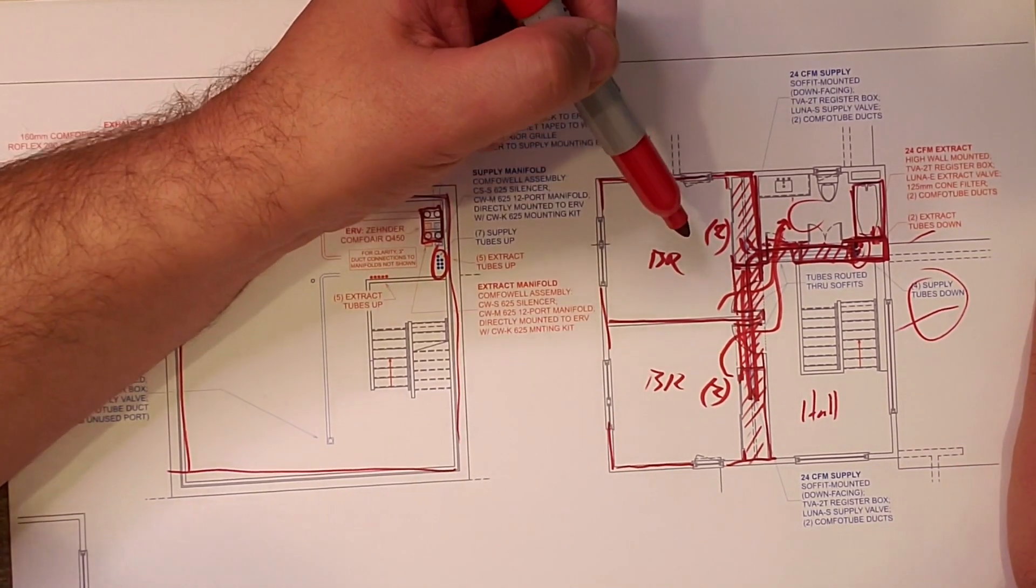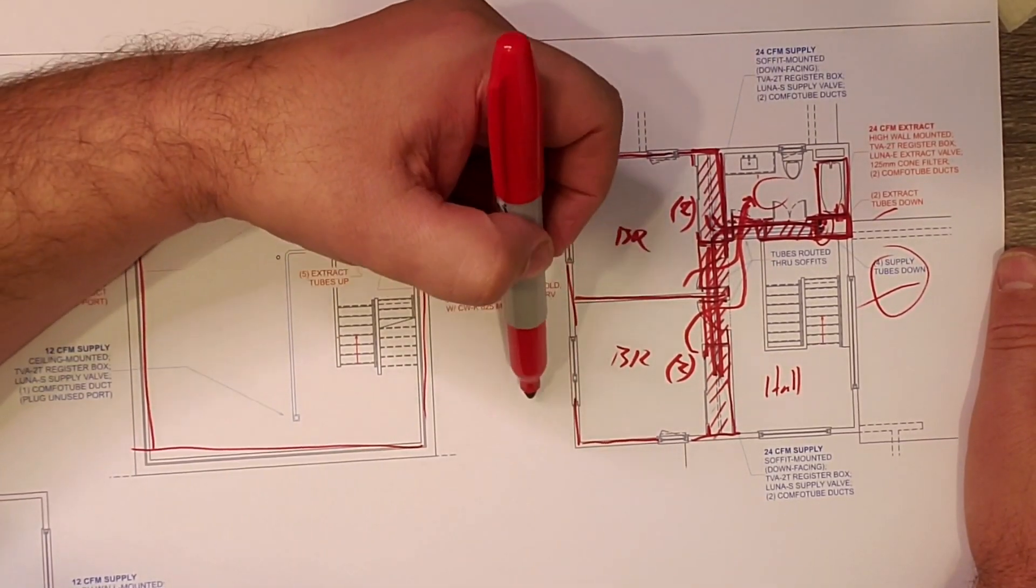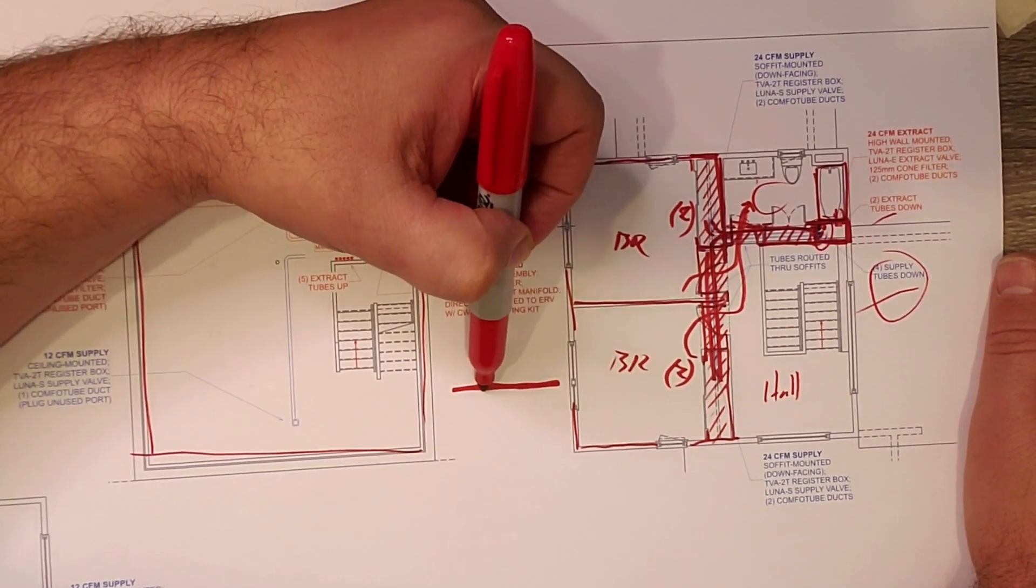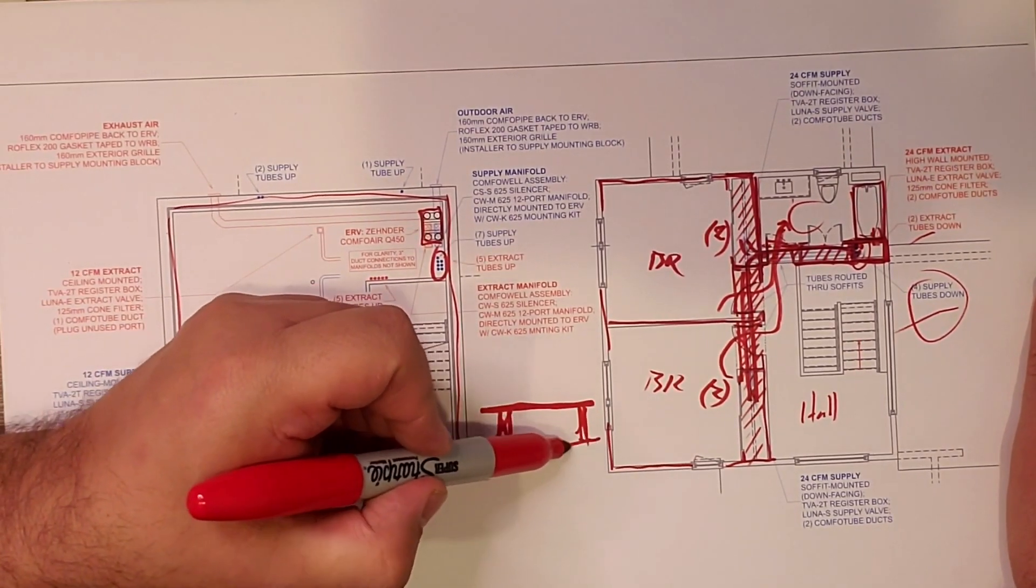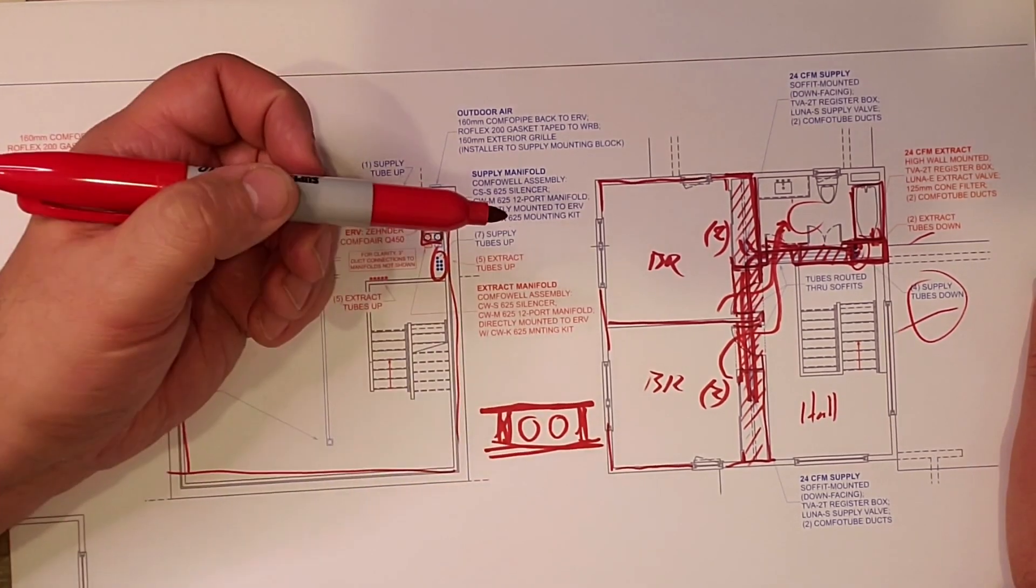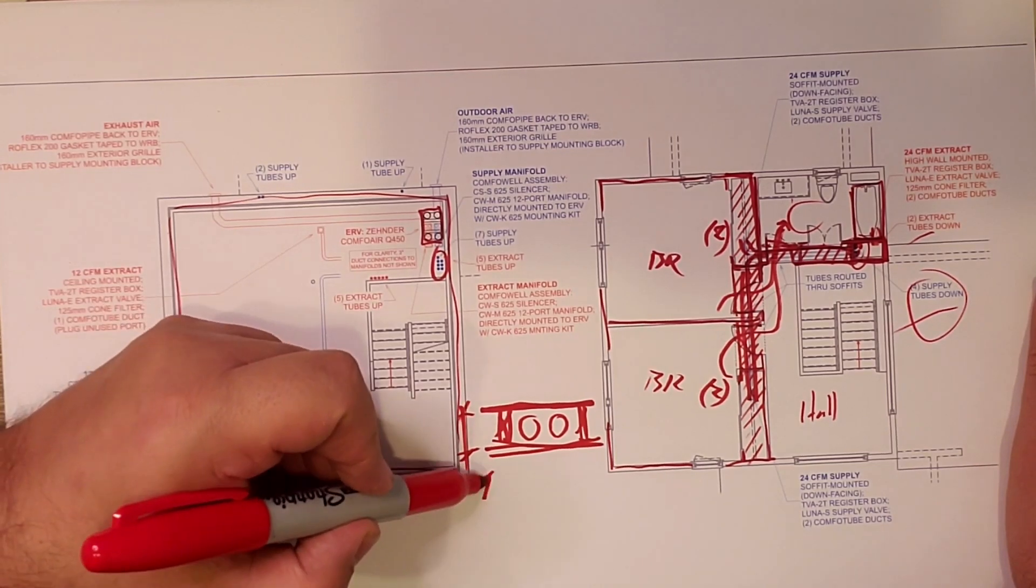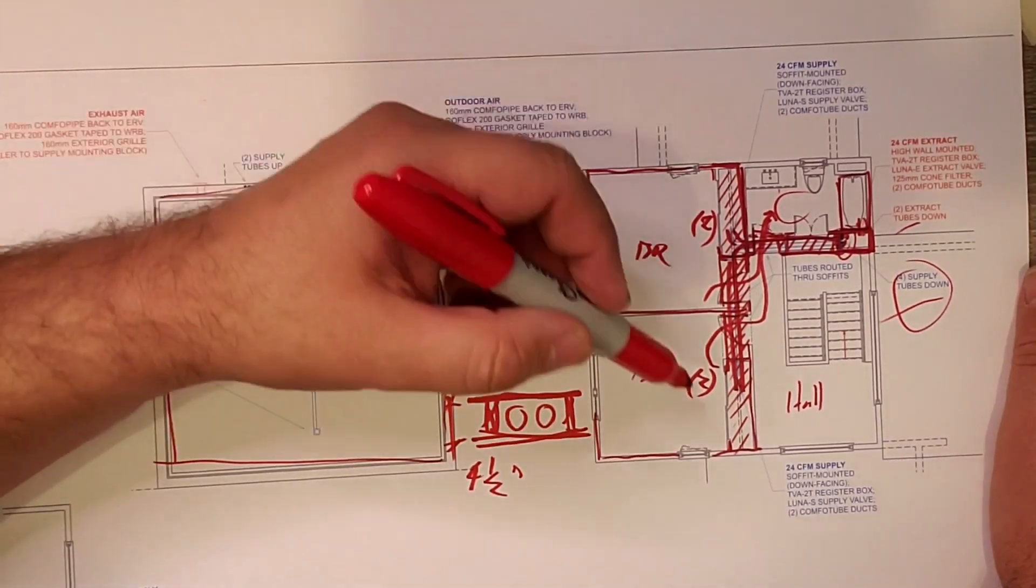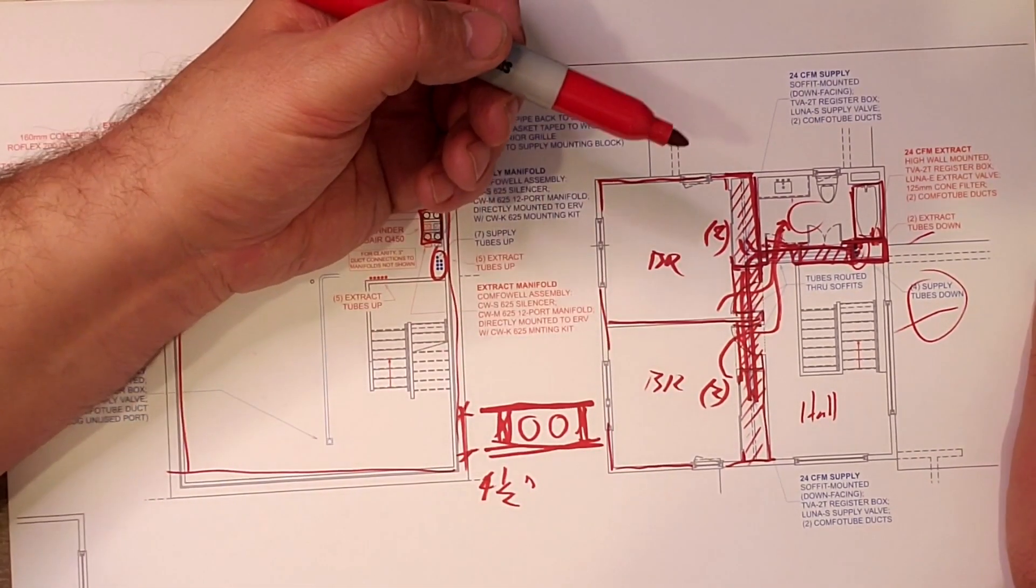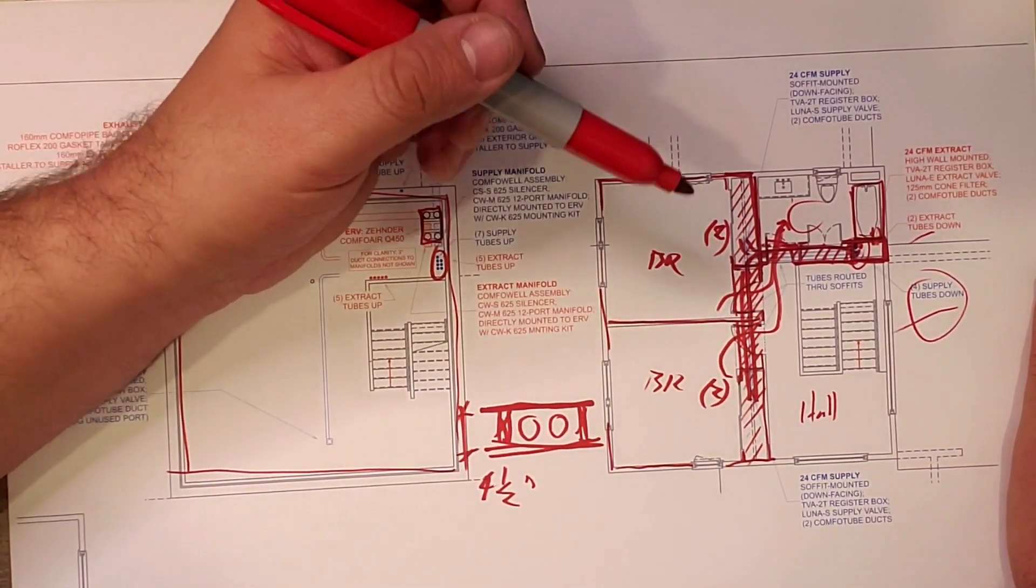That allows us to basically drop the ceiling across here and then build a chase here and drop the ceiling in these areas. So what that allows, as you saw in the video, those pipes come up, they go through that chase and two of them go here and then two of them continue down here. And then the two extraction are up here and they're extracting from the bathroom. So you're supplying here and the idea is that that air will migrate and get pulled back down there.